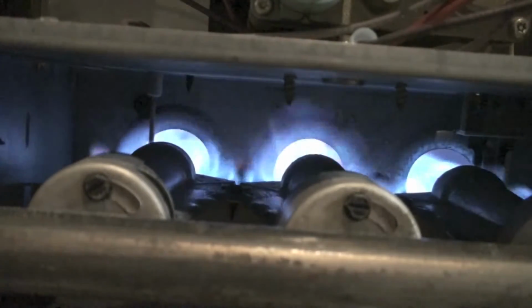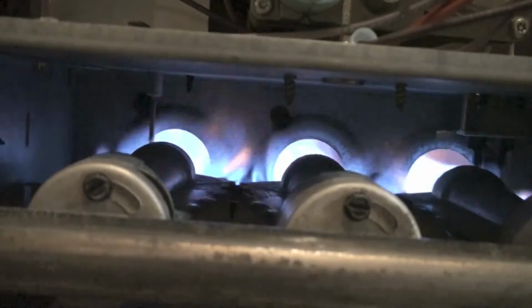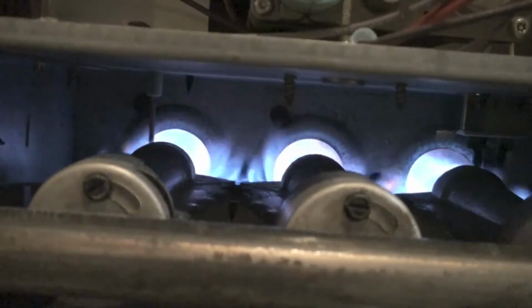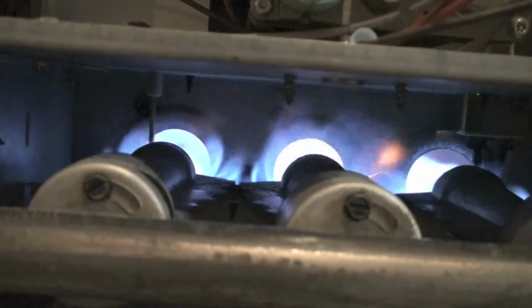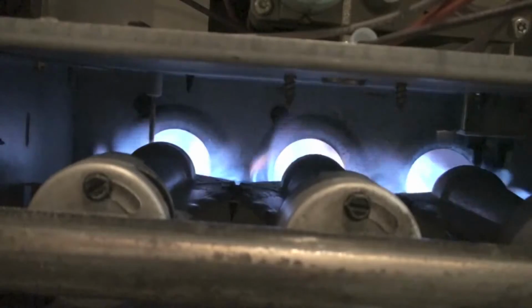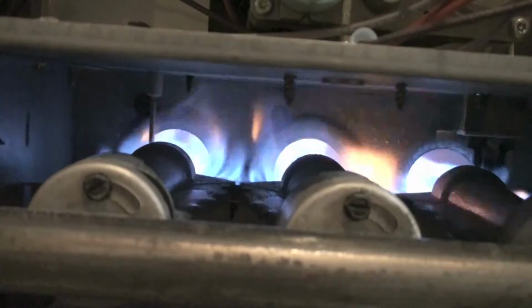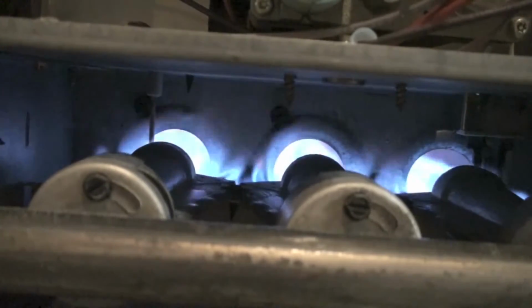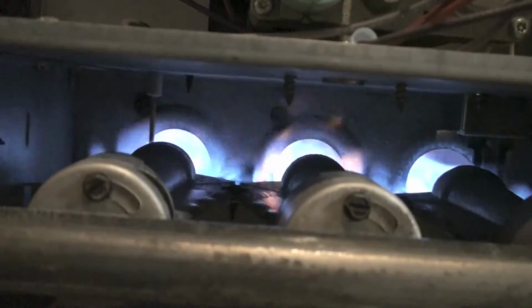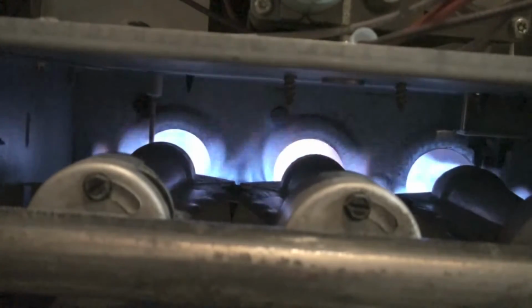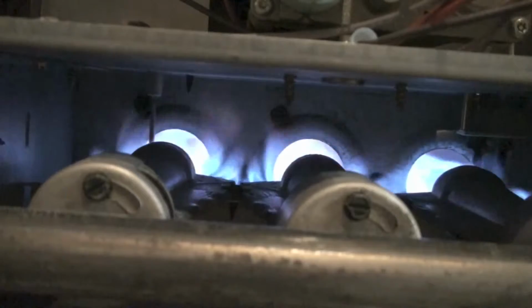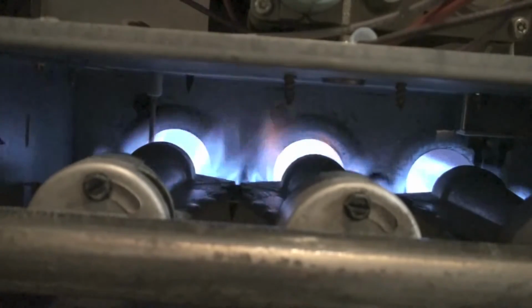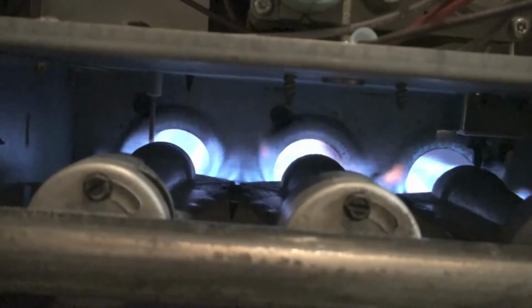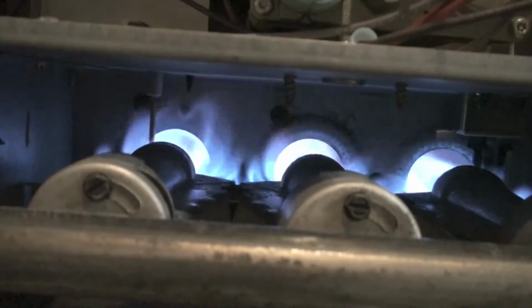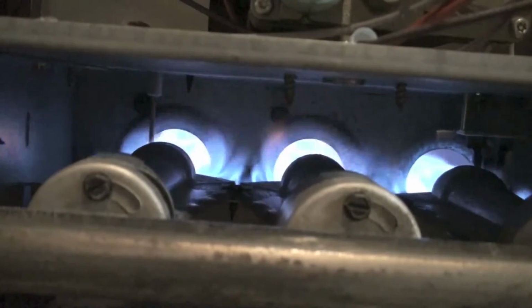Now there is a protective device in these furnaces. If you'll look kind of right above that middle burner, maybe to the right just a little bit, there's a little button up there. Well, that is a rollout switch. And that means if flame rolls out into that chamber up there, then it's supposed to pop off. It's a manual reset. It shuts the machine down and just turns the fan on. Sometimes that would be the symptoms we'd get.